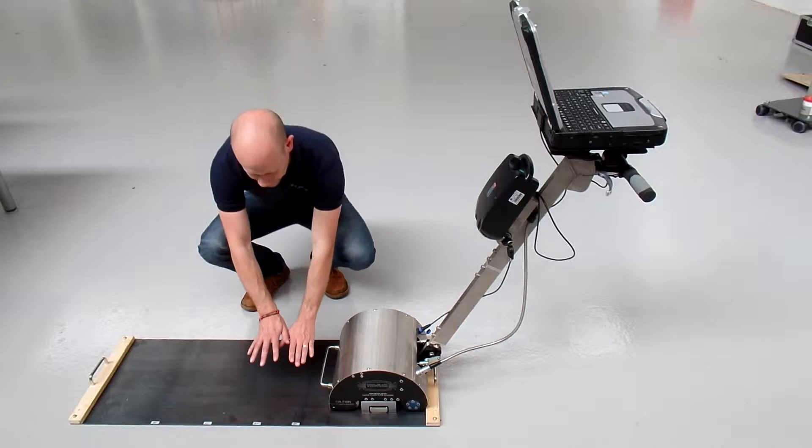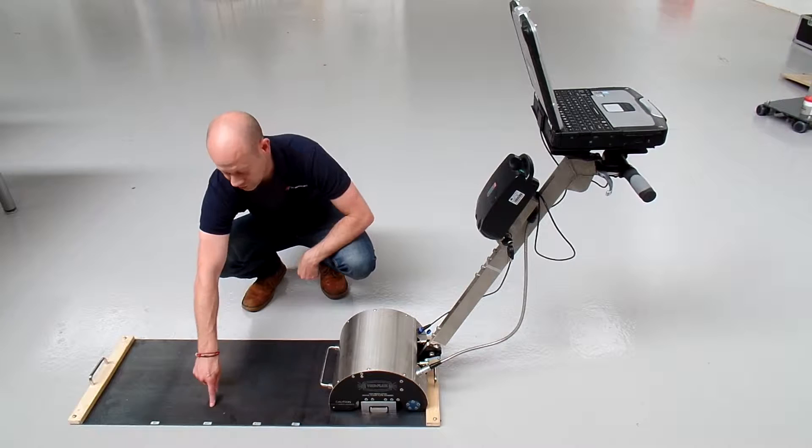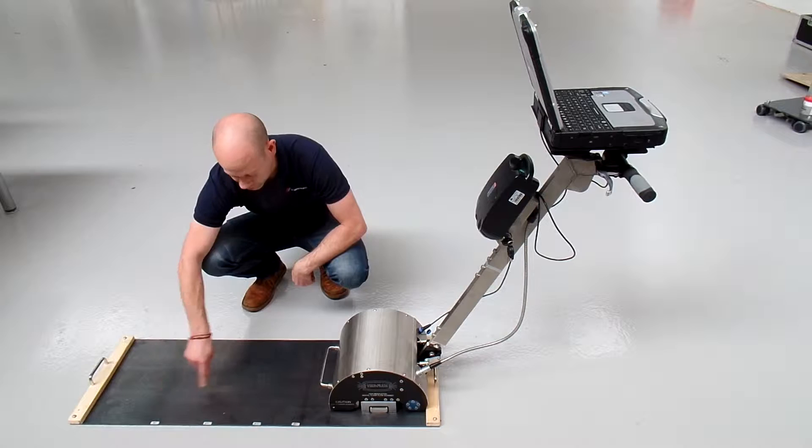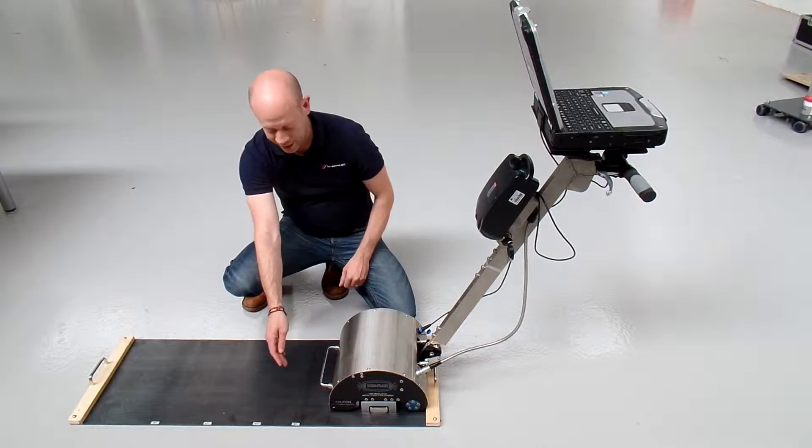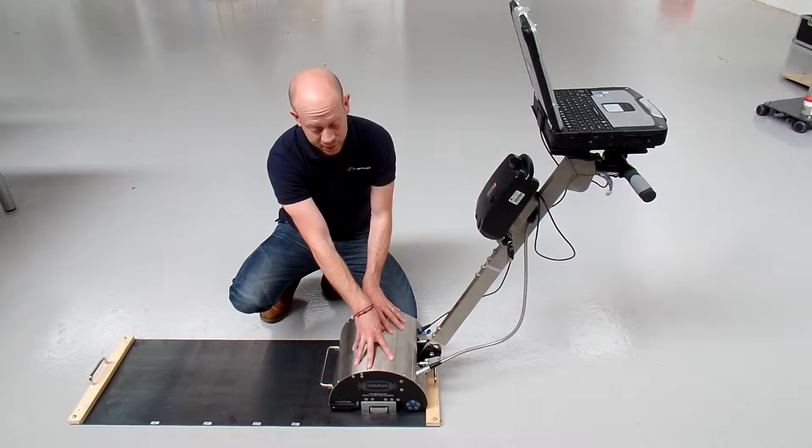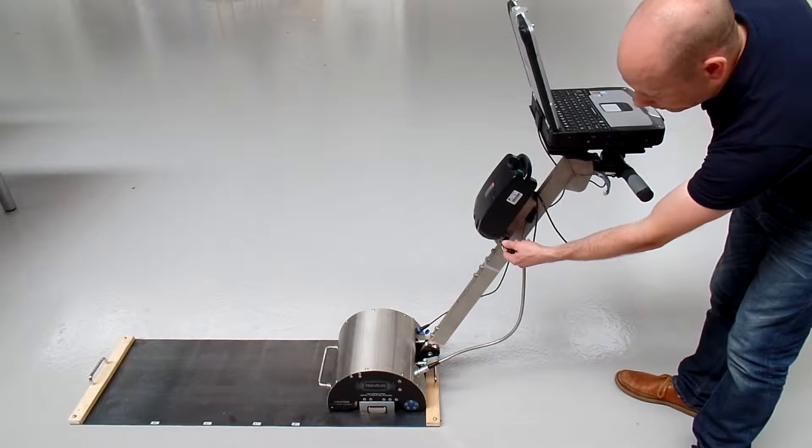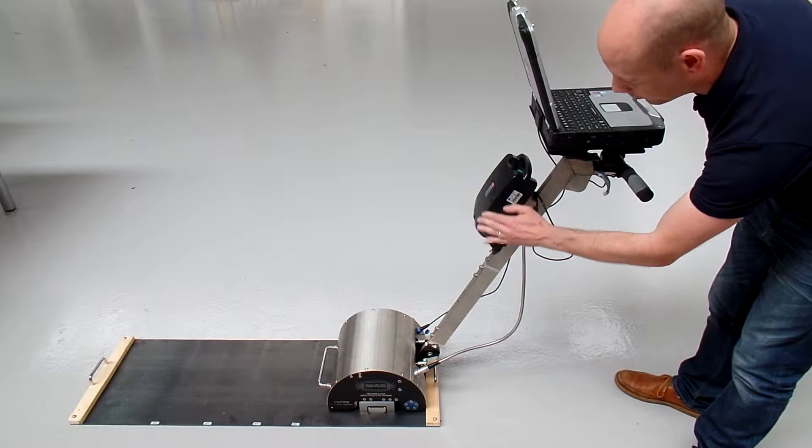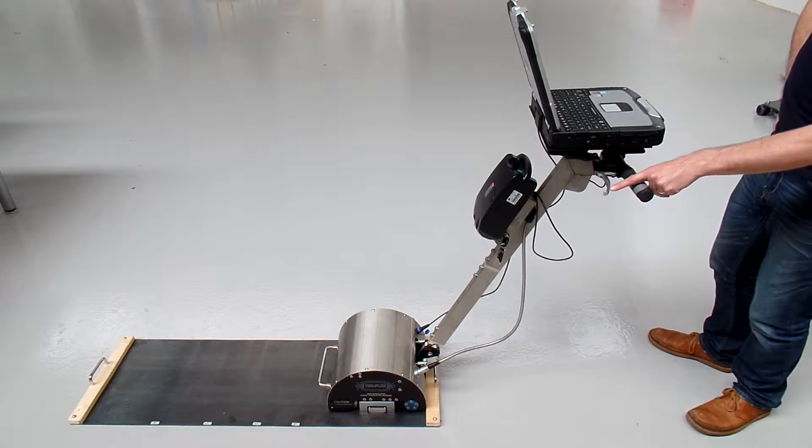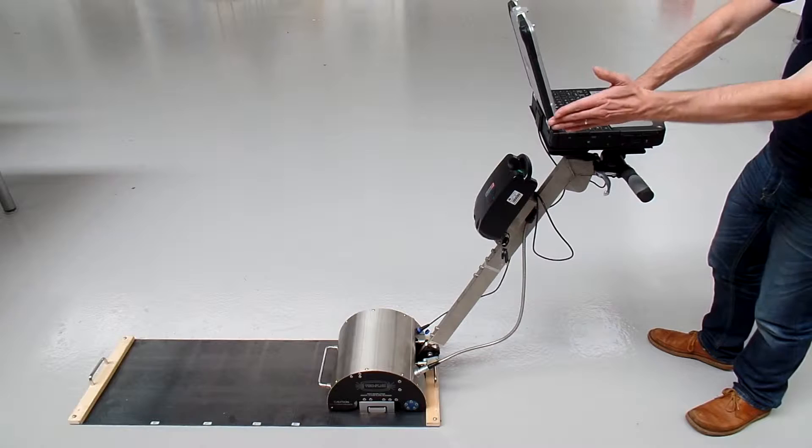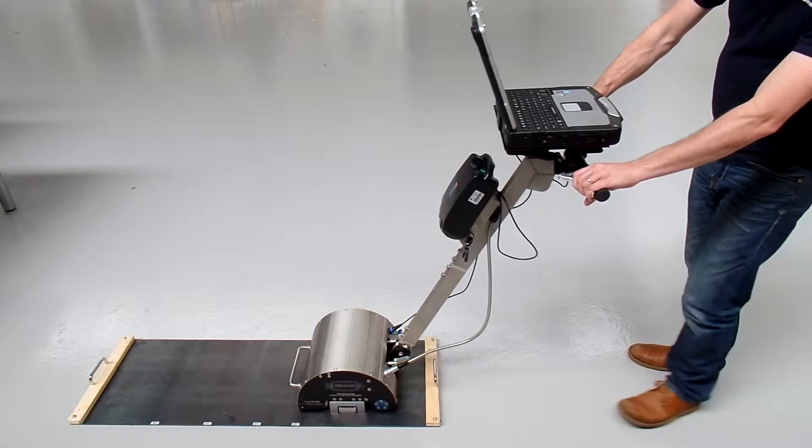The calibration plate is a nominal 6mm, 8mm, 10mm, or 12mm thickness with 20%, 40%, 60%, and 80% through-wall indicators in the rear of the plate. On the right-hand side of the plate, there is an area of nominal plate thickness where the TruFlex unit must be positioned to start a calibration. We're going to do the calibration in this direction from right to left. The unit will look to see the 20% indication first. The power key is rotated all the way clockwise to ensure that power is supplied from the battery to the motors in the head unit.